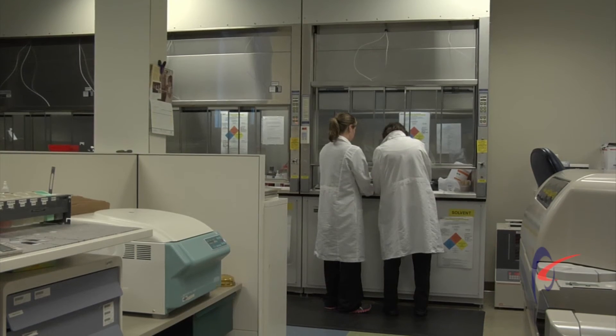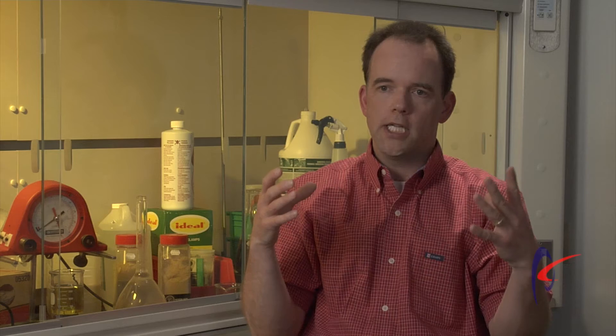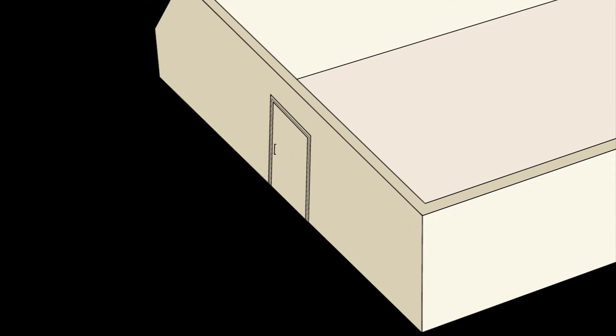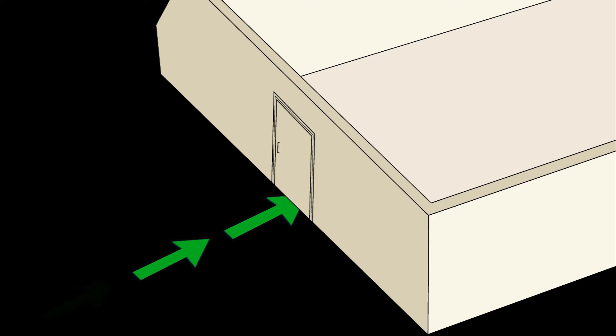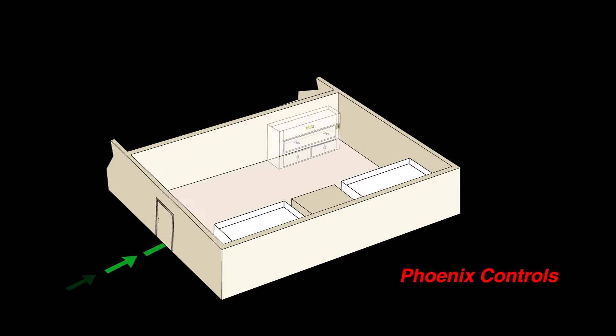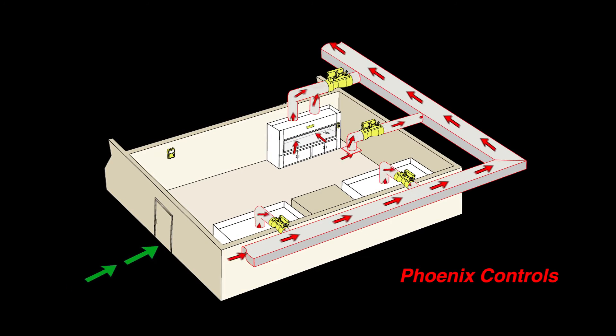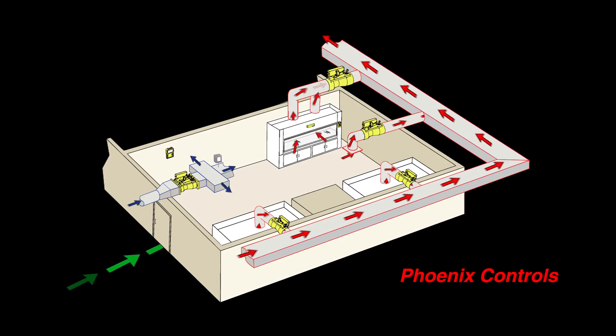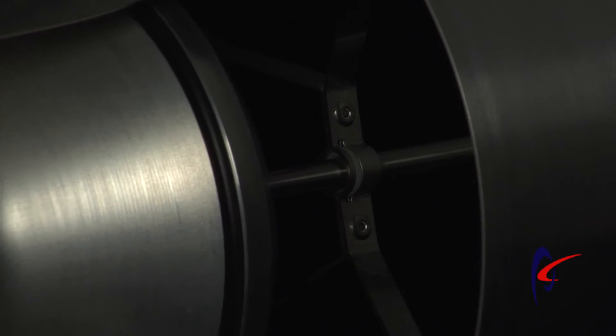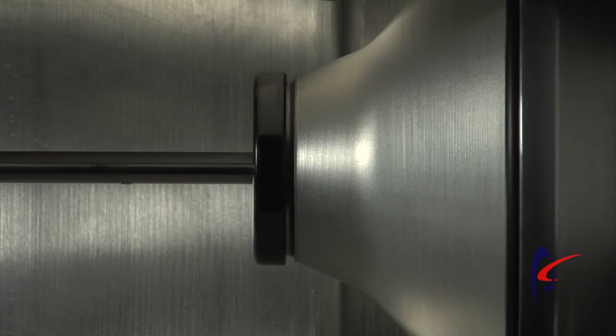After the primary containment zone, the fume hood itself is demonstrated, we'll then take it a larger step. We'll look at the laboratory itself. The lab proper is the secondary containment zone, and so that laboratory must maintain negative pressurization in relation to the corridor or its adjacent spaces at all times. With the Phoenix system, we sum up all the fume hood requirements to that space, the total exhaust signal. The makeup air supplied in that space shall always be something less than that, and that volumetric offset is a fixed volumetric offset. So as a sash position moves, the supply moves with it. As we close that sash, the supply will move down with it, again maintaining that volumetric difference, and therefore the pressurization relationship with the laboratory. If there's ever a spill in that laboratory, the lab will contain it.